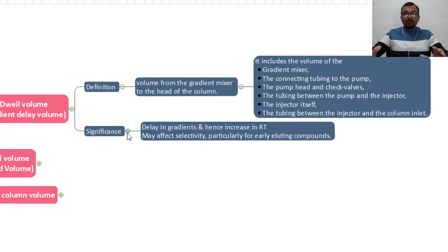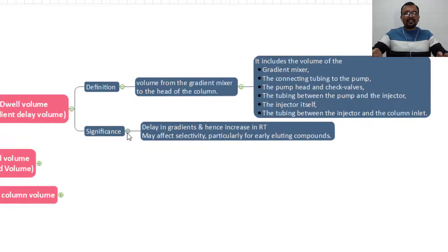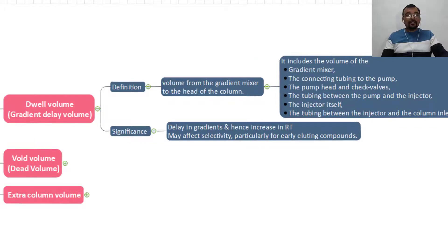Because of that, you may have a delayed retention time, or sometimes you may get different selectivity for the early eluting peaks. It is very important to understand how much the dwell volume of the system is, and what should be the limit for the dwell volume when running a gradient program. Different dwell volumes can result in different chromatographic patterns and different retention times — the more the dwell volume, the higher the retention time.